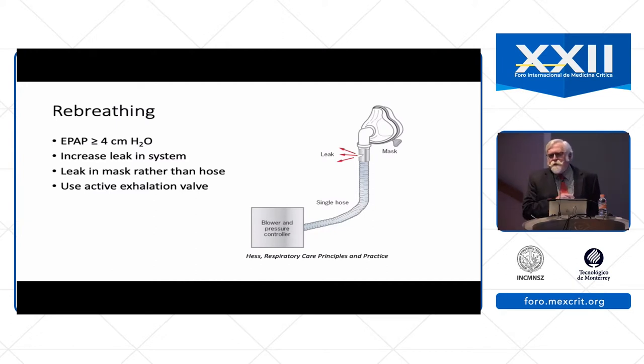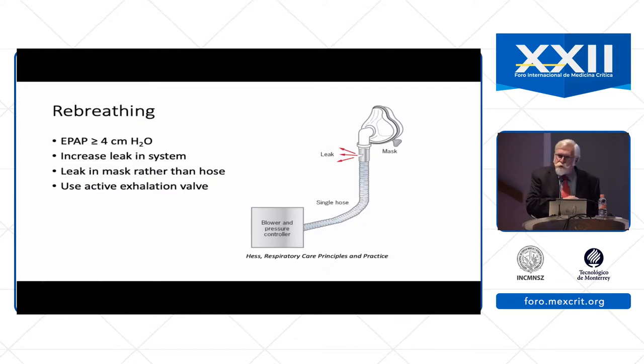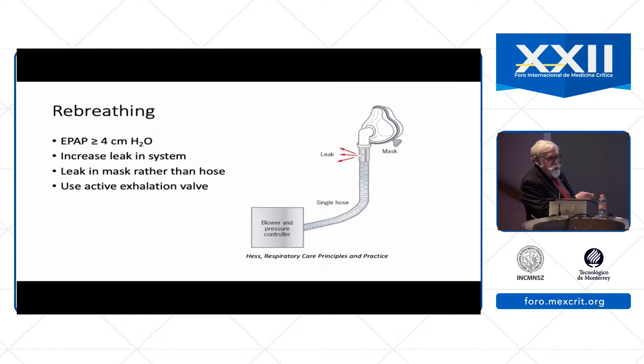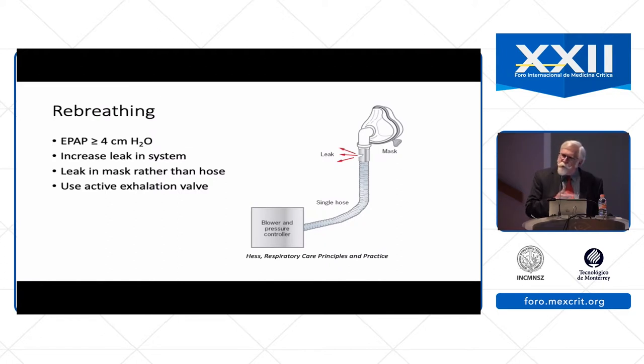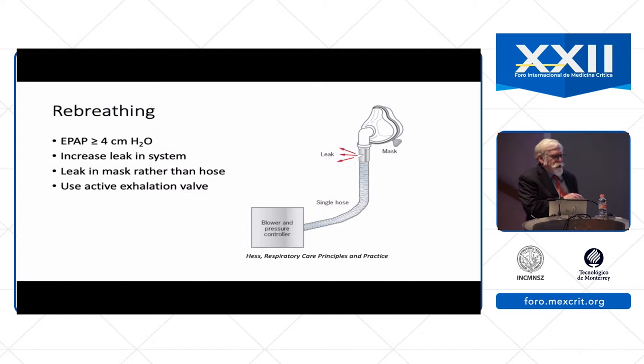One of the issues identified 25 or more years ago with the use of a single limb passive circuit is the potential for re-breathing. If the exhaled breath of the patient exceeds the ability of the leak port to accommodate that exhale, the patient can potentially exhale into the circuit and then re-breathe carbon dioxide on the subsequent inhalation. Certainly, in a patient with hypercapnic respiratory failure, we would prefer that the patient does not re-breathe their exhaled carbon dioxide.